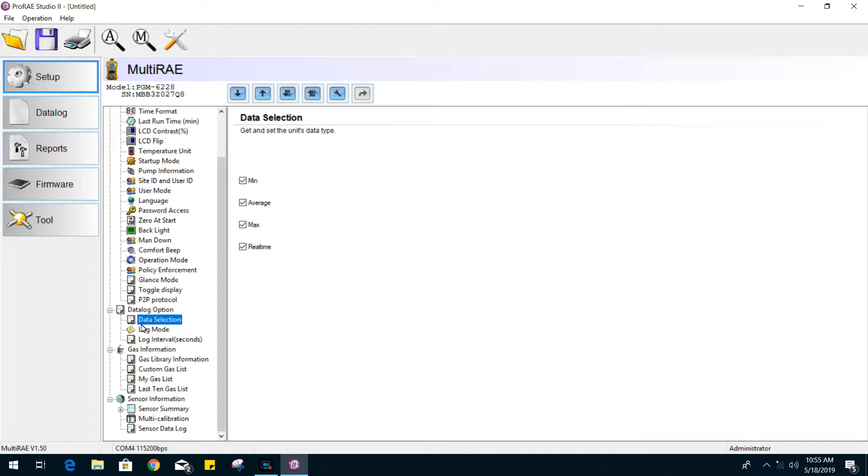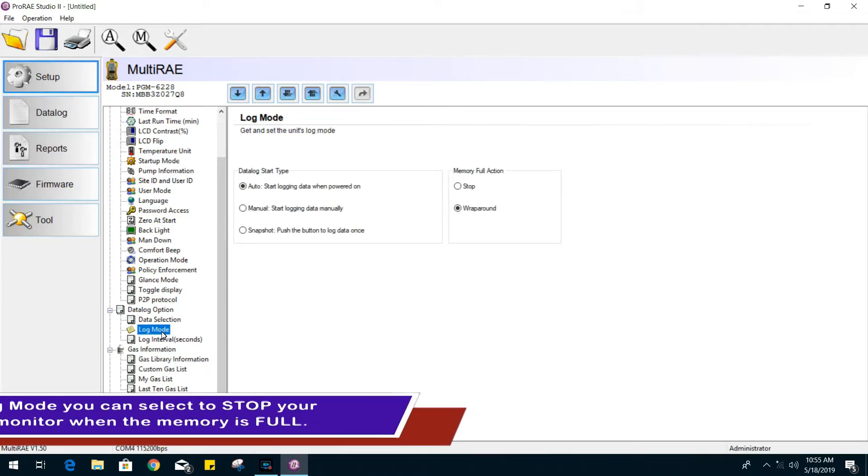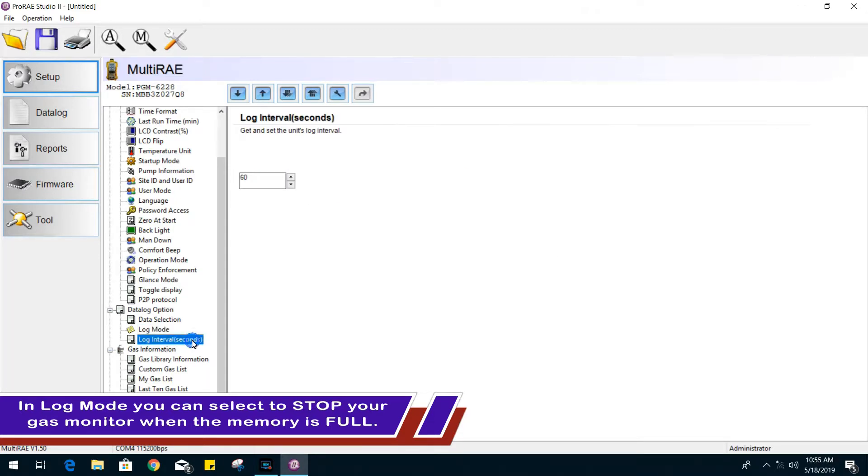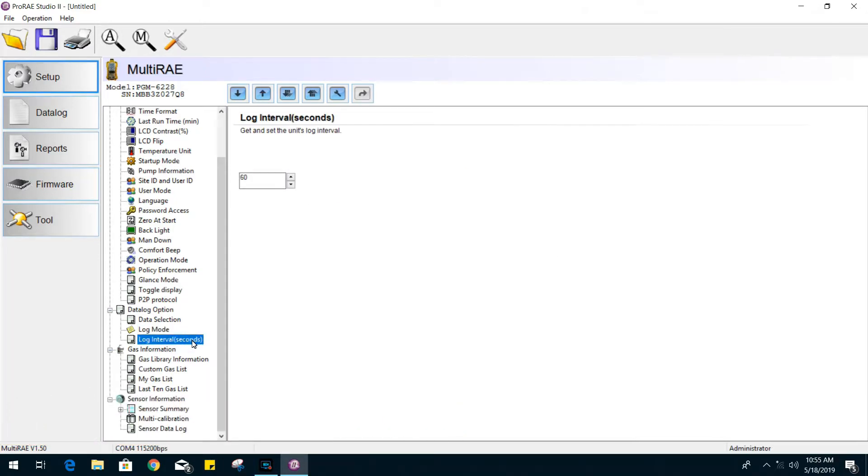Under the data log options, in data selection, you can choose what information you want to keep a record of. For log mode, we are telling the gas monitor when to start keeping record. And for log intervals, we can adjust the frequency rate of recording data. Here, it's set for the default 60 seconds.